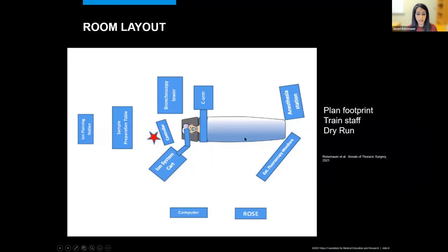This is a room layout of the ION bronchoscopic system. It's a mobile system that essentially attaches to the endotracheal tube of the patient magnetically through a magnetic swivel adapter. The controller is mobile and can be placed anywhere in the room so that the physician doesn't necessarily have to be standing right at the head of the patient. Anesthesia typically moves farther away towards the feet of the patient so that fluoroscopy or any other imaging systems can come into play.